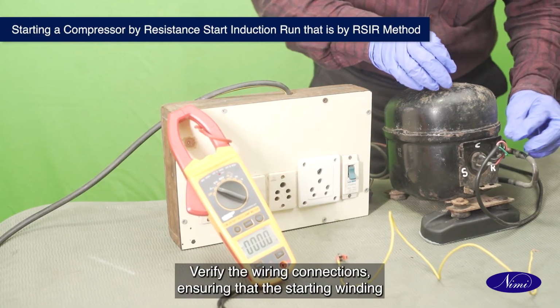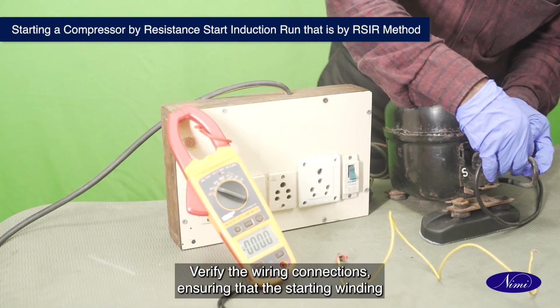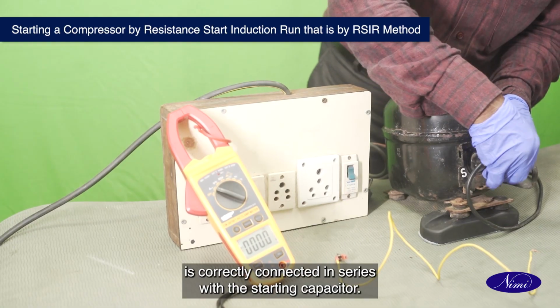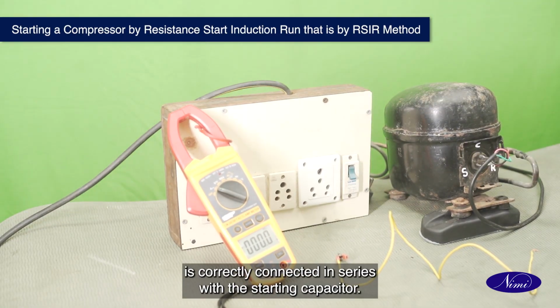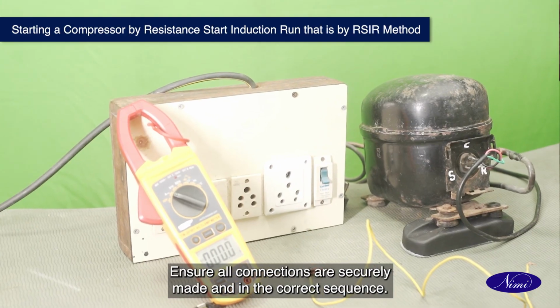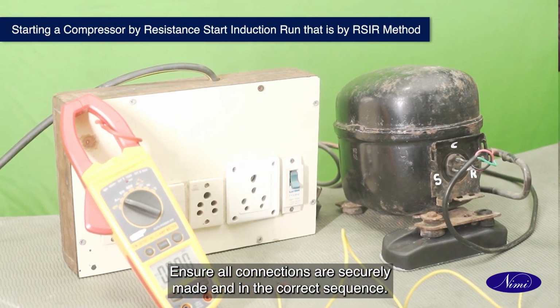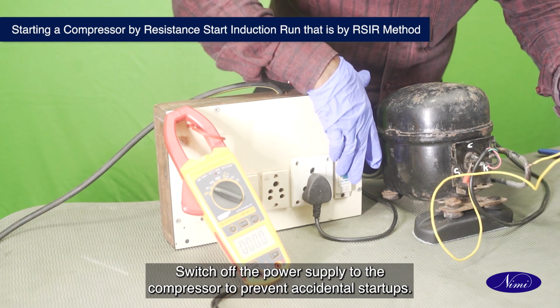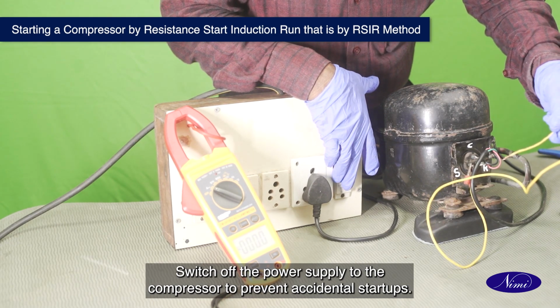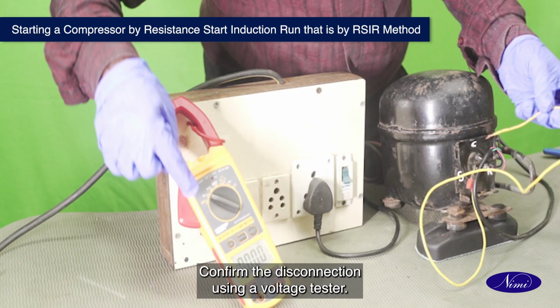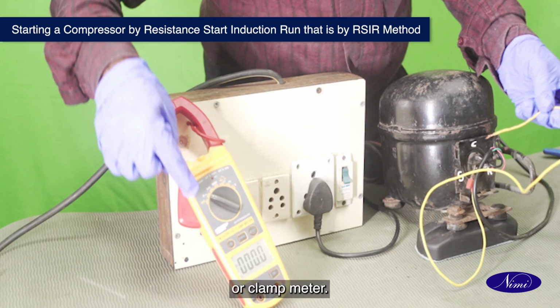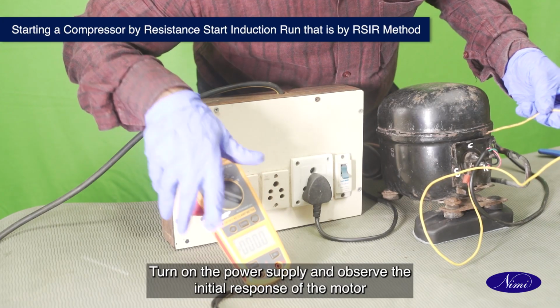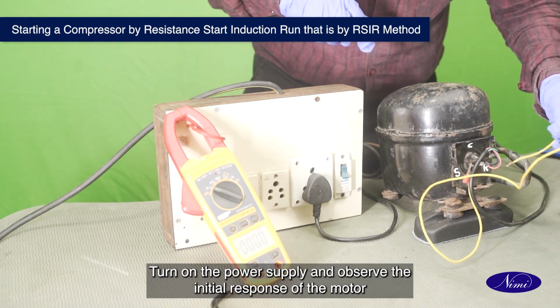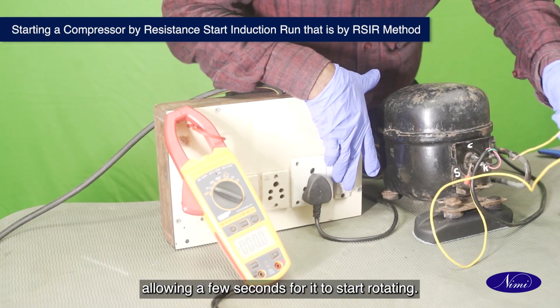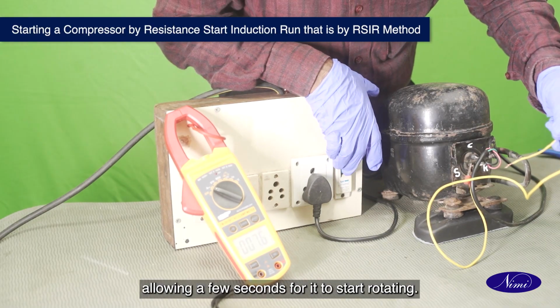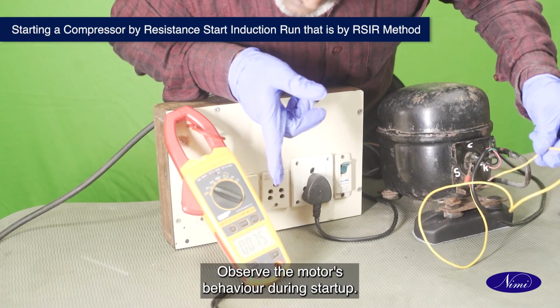Verify the wiring connections, ensuring that the starting winding is correctly connected in series with the starting capacitor. Ensure all connections are securely made and in the correct sequence. Switch off the power supply to the compressor to prevent accidental startups. Confirm the disconnection using a voltage tester or clamp meter. Turn on the power supply and observe the initial response of the motor, allowing a few seconds for it to start rotating. Observe the motor's behavior during startup.